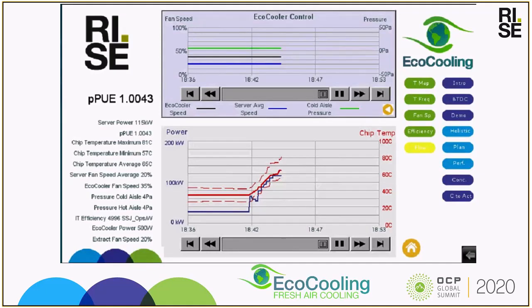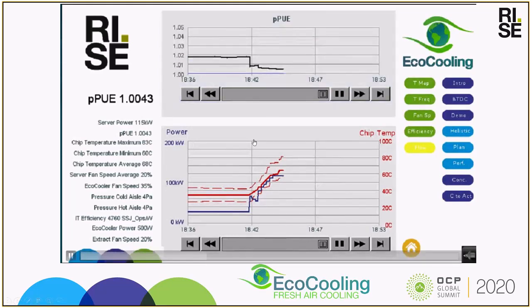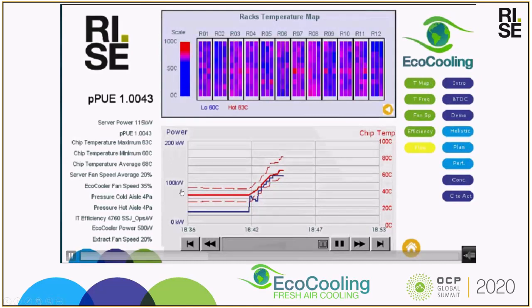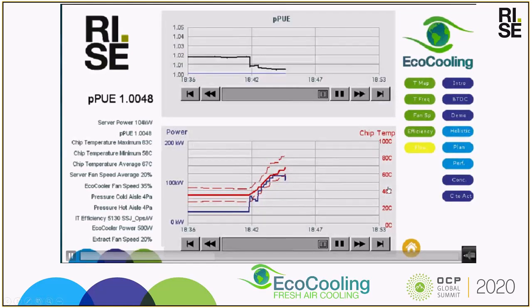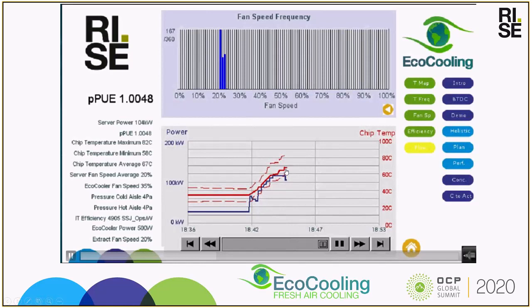Pressure remains stable, fan speeds of the server remain stable, and the fan speeds in the coolers remain stable. So nothing has changed just yet. Everything is under good control as we let the temperature of the CPUs rise. This solid red line here shows the CPU temperatures, red on the right axis here, and this is now reaching its average maximum of around 70 degrees, 67 degrees here.